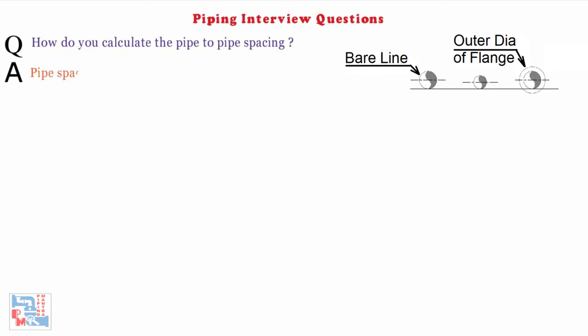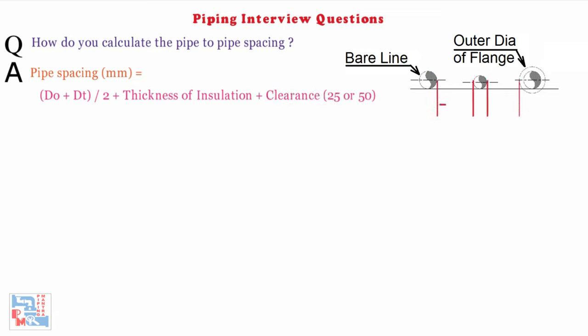Next: how do you calculate the pipe-to-pipe spacing? Pipe spacing in mm equals DO (OD of small size pipe in mm) plus DT (OD of flange of large size pipe in mm) divided by 2, plus thickness of insulation in mm, plus clearance — that is 25mm in case of flanged pipe or 50mm in case of non-flanged pipe. Remember this is the minimum distance required and actual distance should be equal or higher.